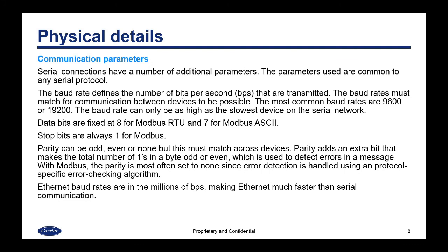Serial connections have a number of additional parameters common to any serial protocol. The baud rate defines the number of bits per second that are transmitted. Baud rates must match for communication between devices to be possible. The most common baud rates are 9600 or 19200. The baud rate can only be as high as the slowest device on the serial network.